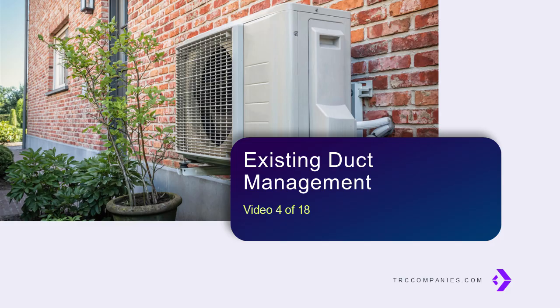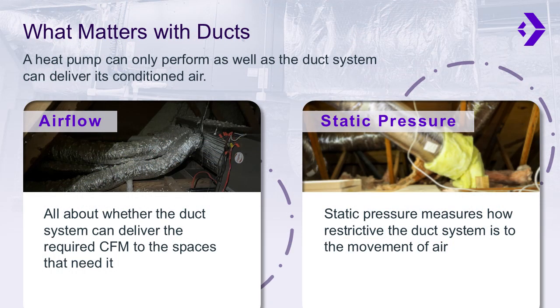Today, we're going to focus on existing duct management. Let's dive right in. Duct sizing is one of the most critical factors to getting the most out of a heat pump. Even a perfectly sized heat pump can't perform efficiently if the ducts aren't sized correctly. Duct sizing directly impacts two key aspects of system performance: airflow and static pressure.